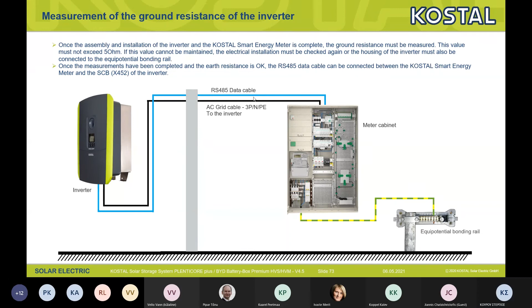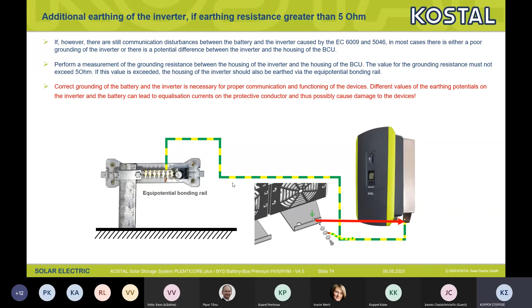Then go to the battery settings and choose BYD as the battery. That's the two steps you need to do. For communication, make sure the ground is okay, meaning less than 5 ohms. If it's more than 5 ohms, there may be communication problems between the inverter and the battery. So please troubleshoot, measure the earthing resistance, and make sure everything is okay there. That's it for the battery commissioning.